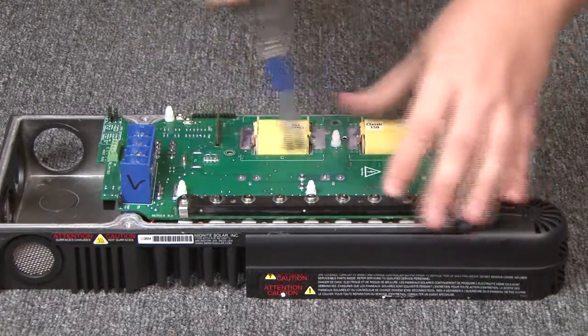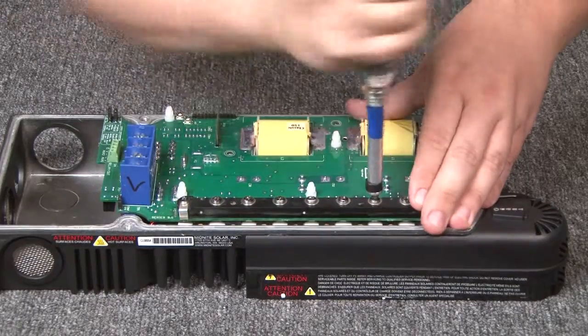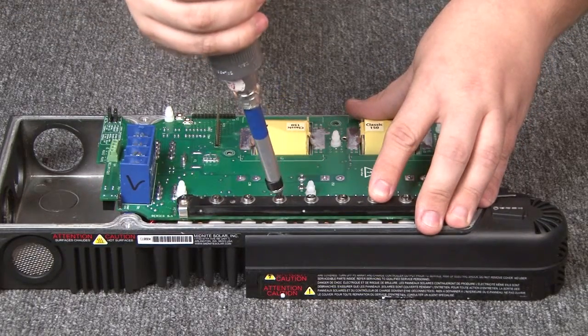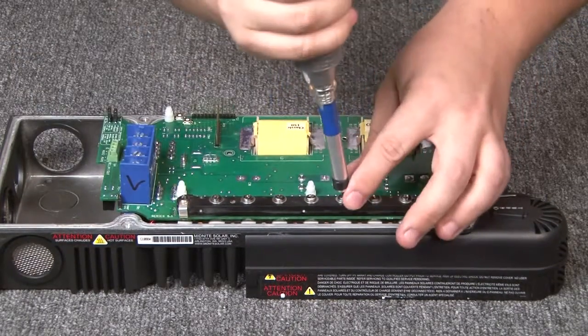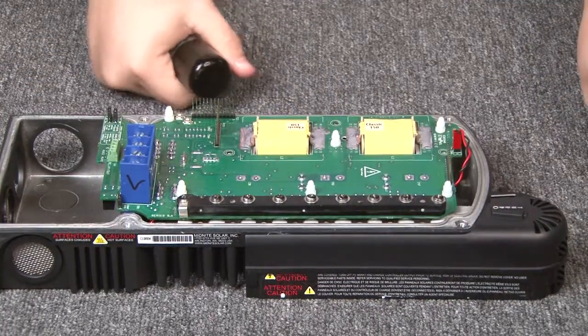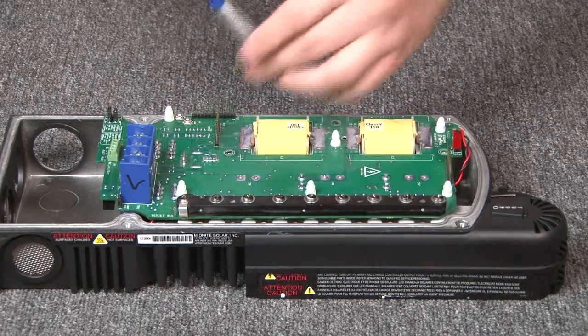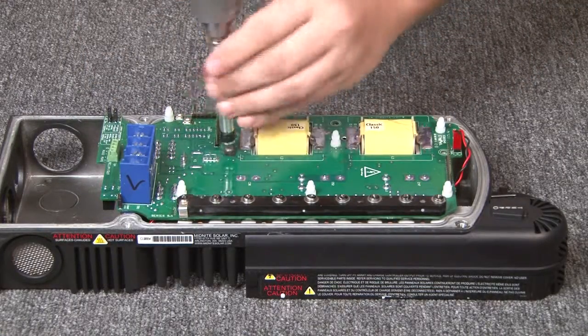This is a good time to point out that the cracking in the FET bar is normal. You also want to make sure that you are using 18 inch-pounds. Now we are going to reinstall the three screws here — they do not need to be torqued, they just need to be snug.